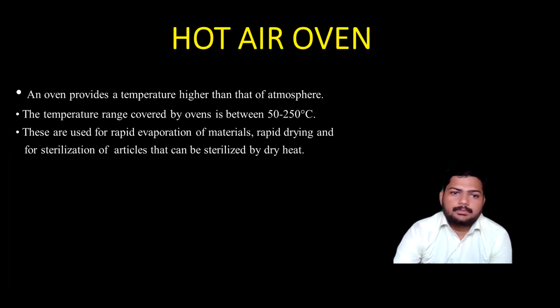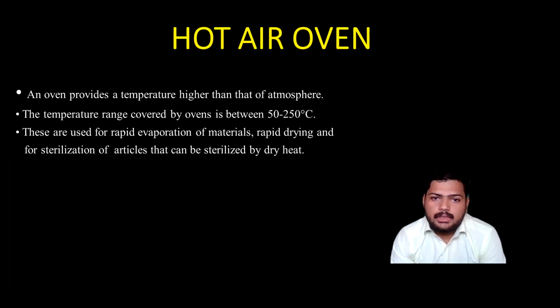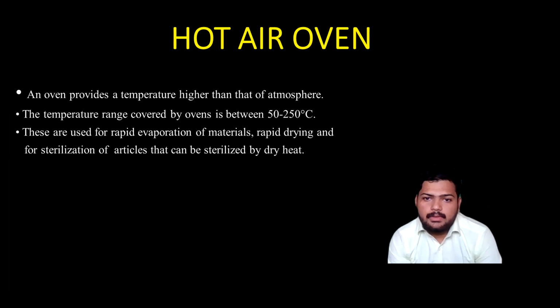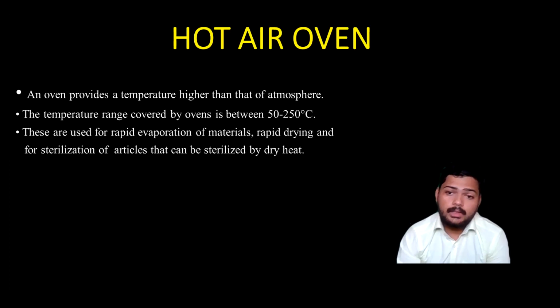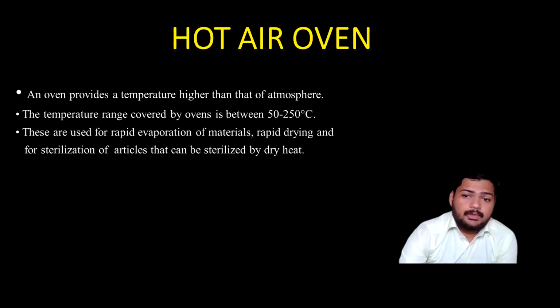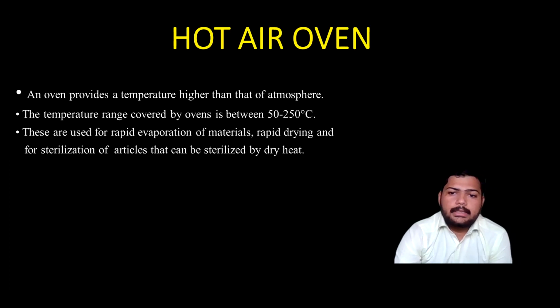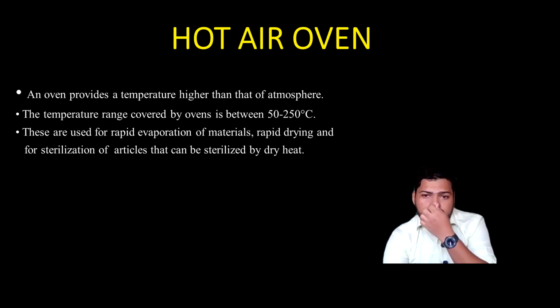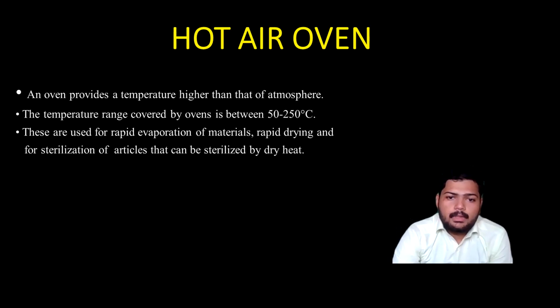Next is the hot air oven. An oven provides a temperature higher than that of the atmosphere. The temperature range covered by the oven is between 50 to 250 degrees Celsius. These are used for rapid evaporation of materials, rapid drying, and for sterilization of articles that can be sterilized by dry heat. This is used to increase the temperature, and some solutes and powder samples are sterilized by this method.